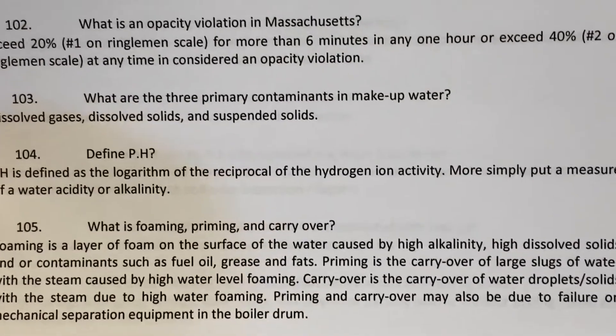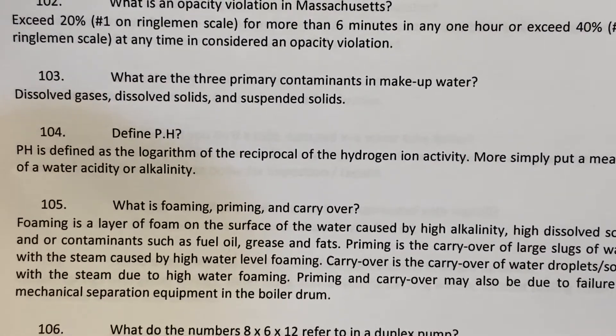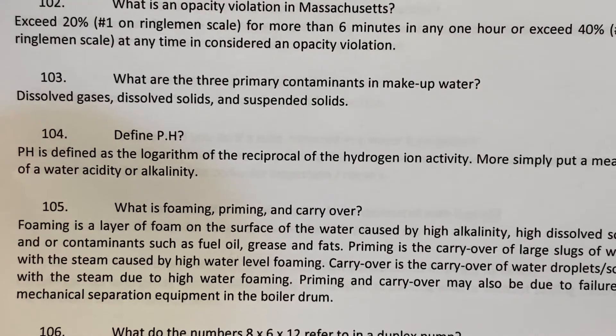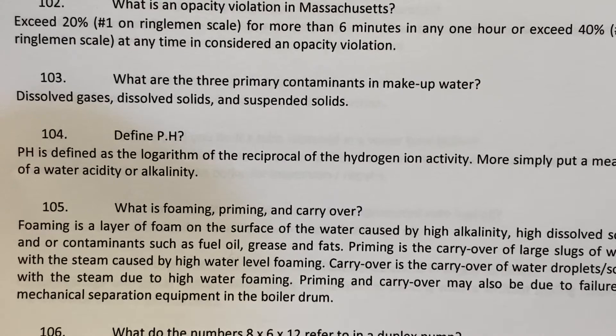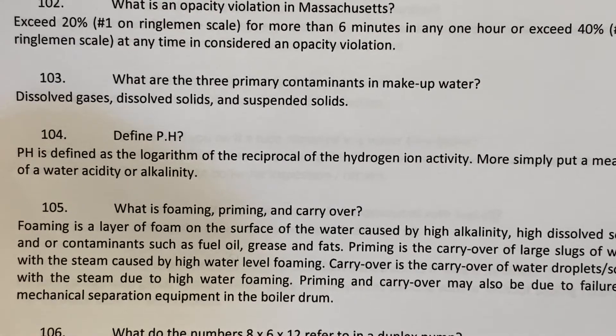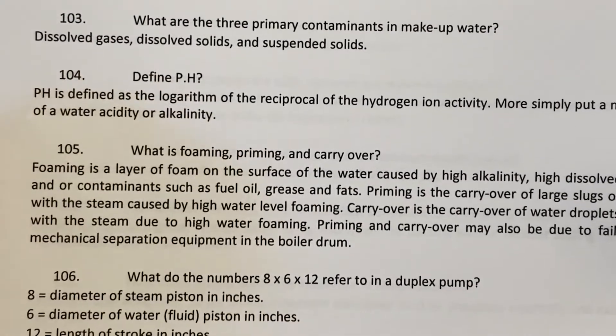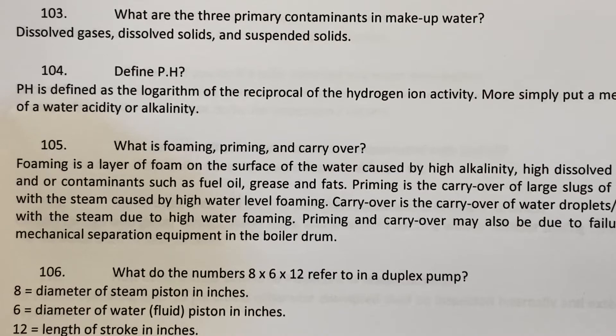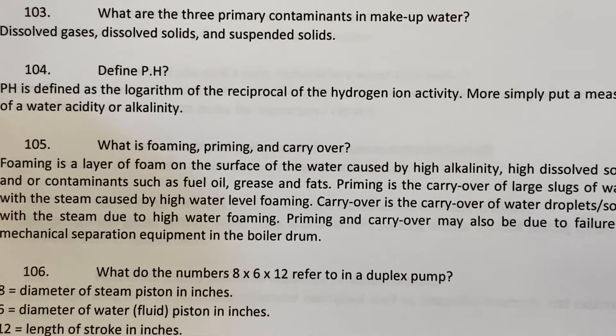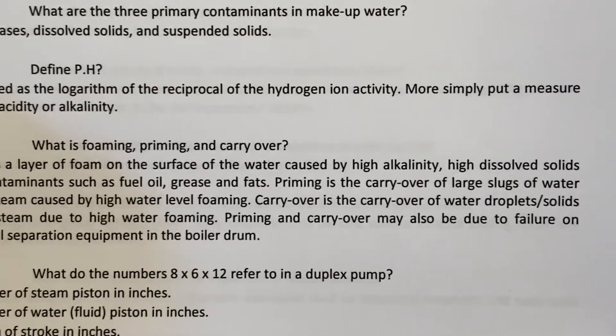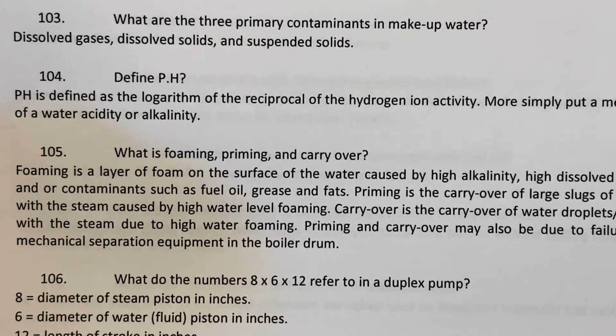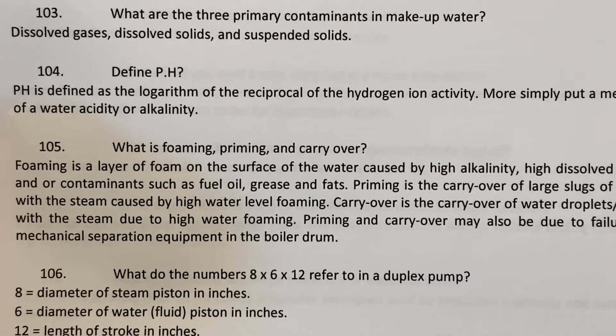What are the three primary contaminants in makeup water? Dissolved gases, dissolved solids, and suspended solids. Define pH: pH is defined as the logarithm of the reciprocal of hydrogen ion activity — more simply put, a measure of water acidity or alkalinity.